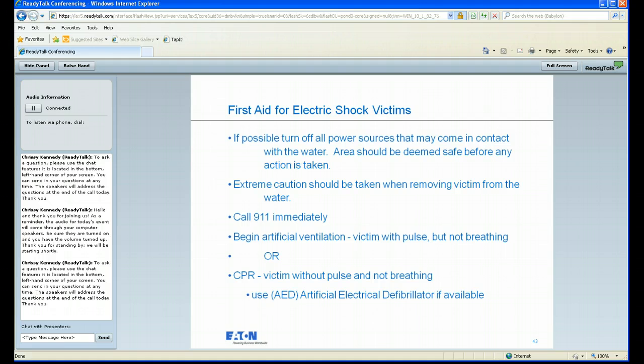Some first aid for shock victims. This was some stuff that we found off the internet. Basically, the most important thing to know is that if you have an area where you're noticing tingling in the water, or if you notice someone come in contact with some electrical current, the most important thing is to make sure that all power sources are turned off immediately. No one should enter the water until that area has been deemed safe first.